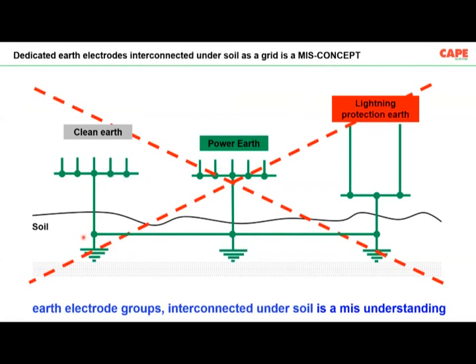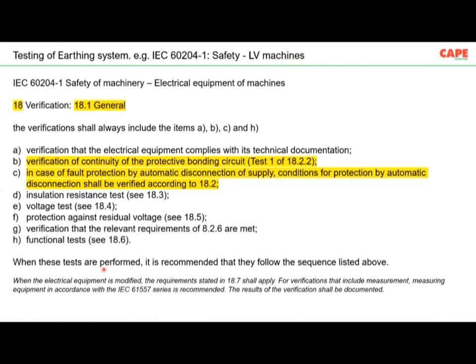So earthing must be done as per the picture which I have shown in one of my last slides. The exposed and extraneous conductive parts of the installation must be connected to the main earthing terminal of that particular installation through different conductors called the protective earthing conductor, protective bonding conductor, supplementary bonding conductor, and so on. The impedance of these wires, the continuity resistance of these wires, is extremely important. Now I will show you how to make earthing.